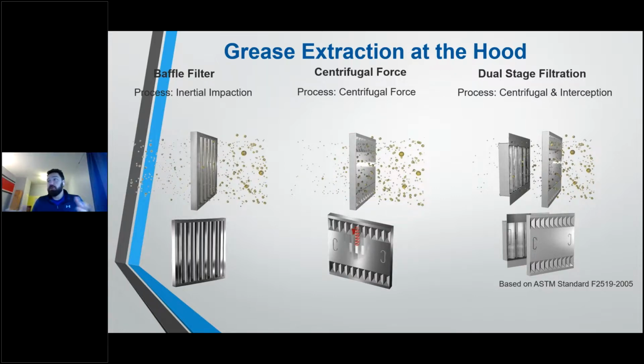So the baffle filter was the traditional way, and really the only way that you could do grease filtration. Not very efficient. It's going to allow for a lot of grease to escape into the ductwork, and it's really not intended to do filtration. So what the industry has moved to, depending on manufacturer, is a centrifugal force type of filter, which is going to spin that air and get the grease to drop out. These are typically anywhere from 60 to 70 or 80% efficient. And that's just going to be a much higher filtration level with a slight uptick in cost, but very low negative impact on your static pressure, so low negative impact to horsepower.